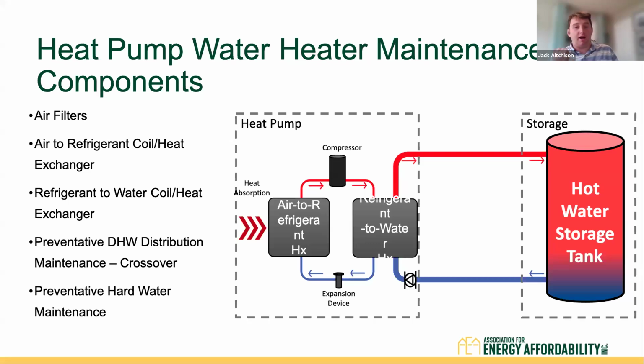So, items to maintain on a heat pump water heater. You have your air filters, you have your air to refrigerant coil slash heat exchanger, you have your refrigerant to water coil heat exchanger. These are effectively very similar to a heat pump HVAC, and the way that you maintain these is very similar. Cleaning the air filters, inspecting the heat exchanger coils, cleaning the heat exchanger coils. Now, one thing I will note, in the slides that go into more detail on how to actually maintain this equipment, there is a yellow tag that says difficult. That flags the difficulty to help you decide whether you would like to maintain this through a contractor or do it with site staff, depending on the nature of your building and who's there at your building, who works there.